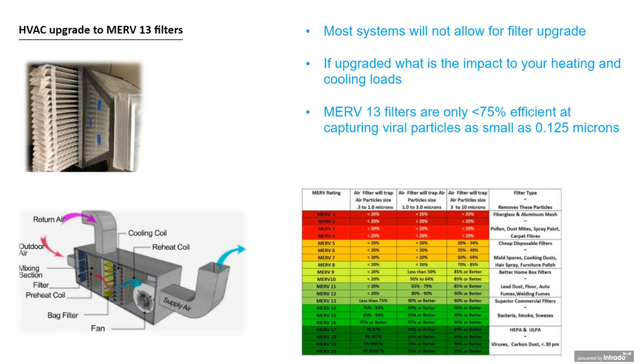So MERV 13 filters, again, I told you I would discuss the MERV rating filters later on in the presentation. As I mentioned earlier, the MERV 13 filters are about 75% efficient at capturing viral particles as small as 0.125. 75% is not great, but it's not horrible. If we look at a MERV 7 filter, which is the standard filter that's usually within facilities and how an HVAC is designed, you have less than 20% efficiency at microns smaller than 0.3. As you get larger in the micron size, it becomes more efficient, obviously because the particle itself is larger.